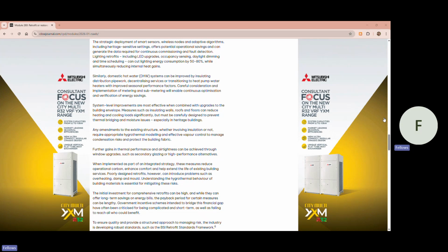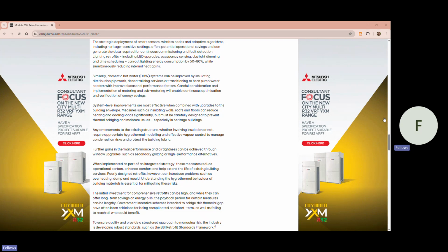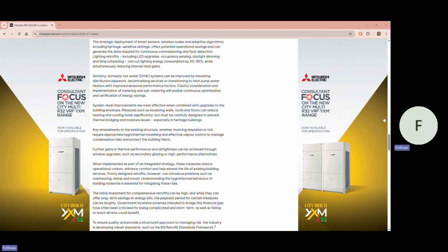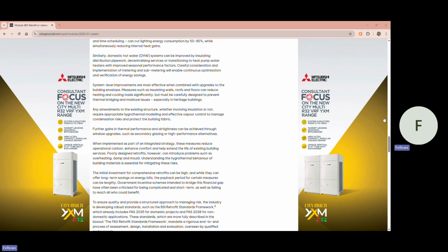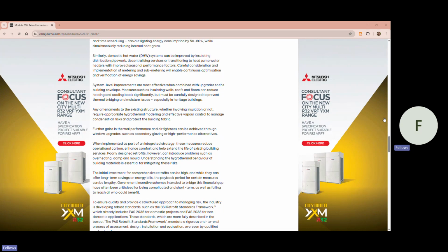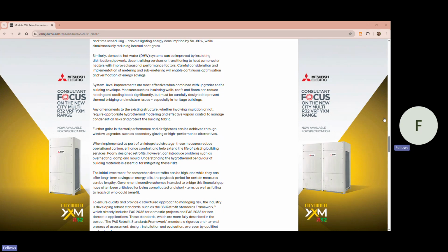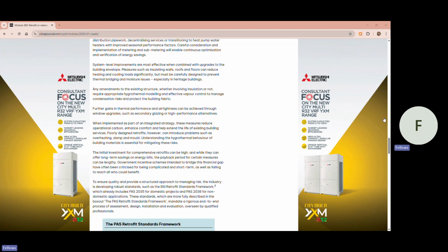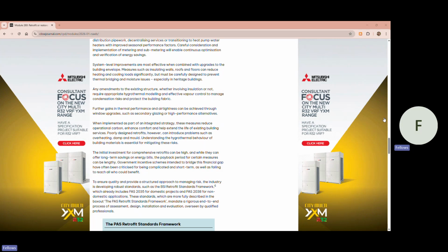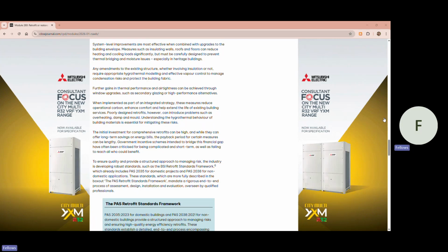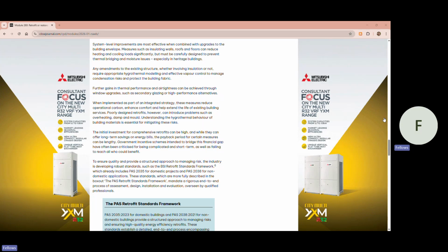Measures such as insulating walls, roofs, and floors can reduce heating and cooling loads significantly, but must be carefully designed to prevent thermal bridging and moisture issues, especially in heritage buildings. Any amendments to existing structure, whether involving insulation or not, require appropriate hygrothermal modeling and effective vapor control to manage condensation risks and protect the building fabric. Further gains in thermal performance and airtightness can be achieved through window upgrades, such as secondary glazing or high-performance alternatives. When implemented as part of an integrated strategy, these measures reduce operational carbon, enhance comfort, and help extend the life of existing building services.